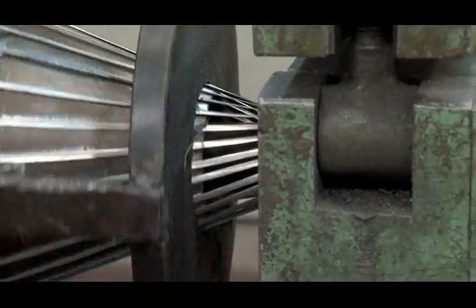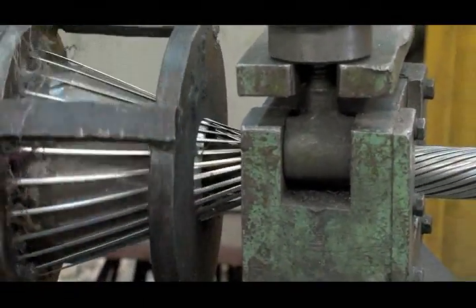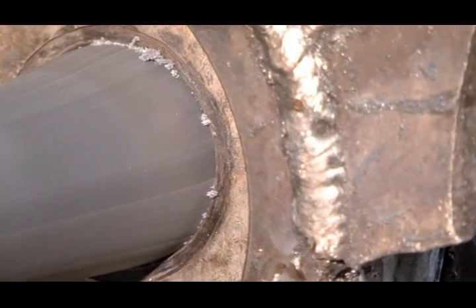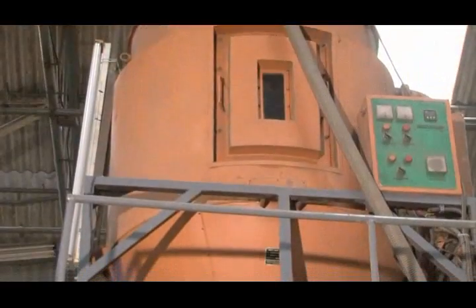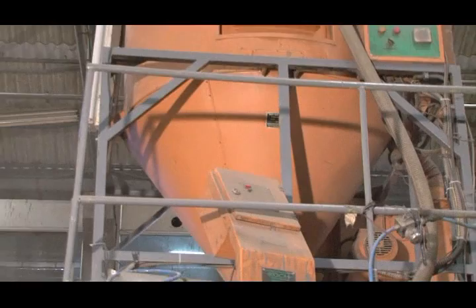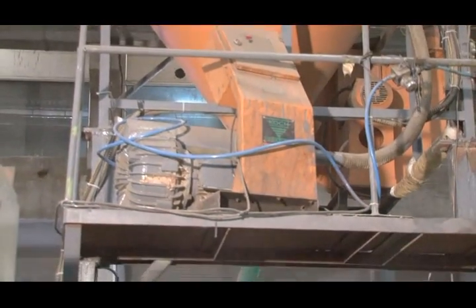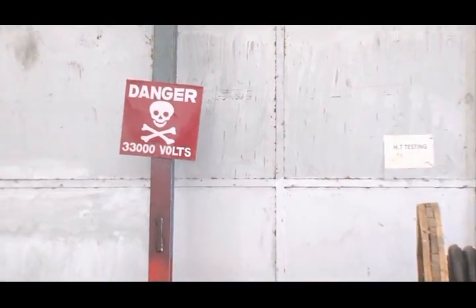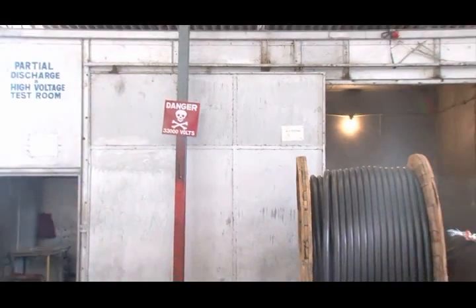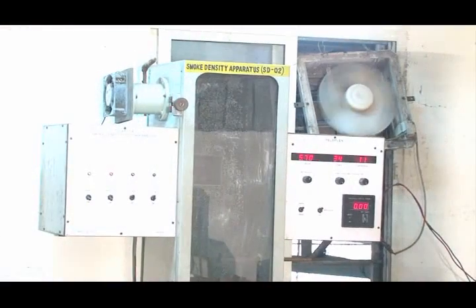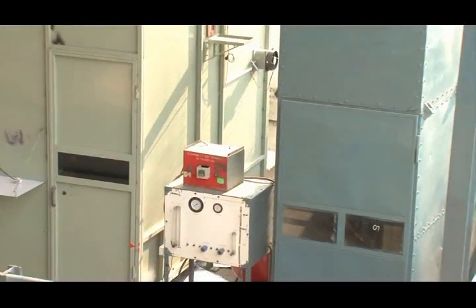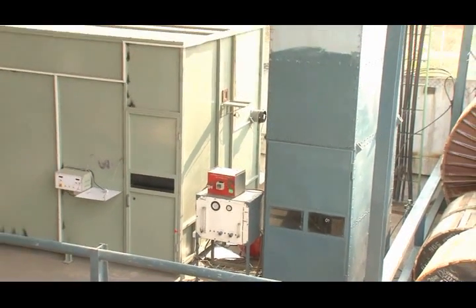Galvanized steel wire armoring is provided over the inner sheath. A tough outer sheath of heat-resistant PVC compound as per IS 5831 is extruded over the armoring. The core identification complies with the requirements of IS 7098. For quality assurance, the high-voltage cables also pass through type and routine tests in accordance with IS 7098.